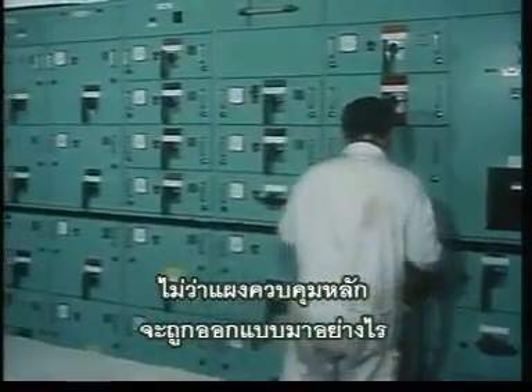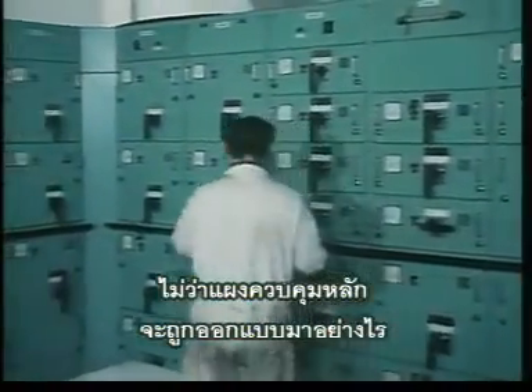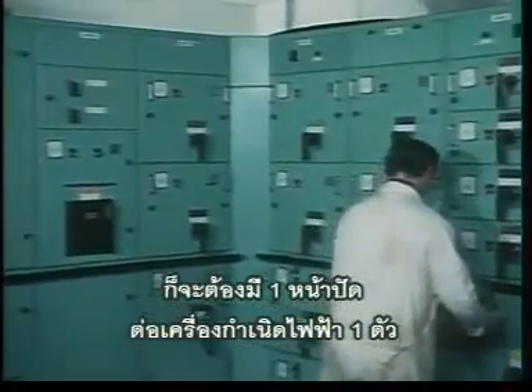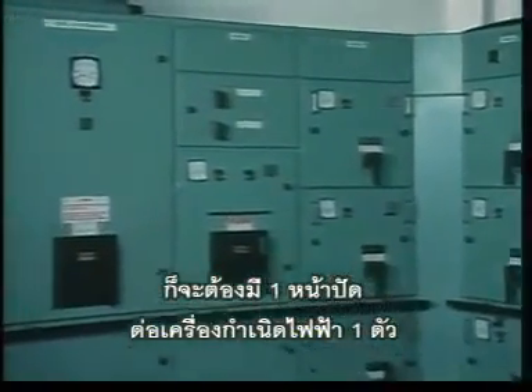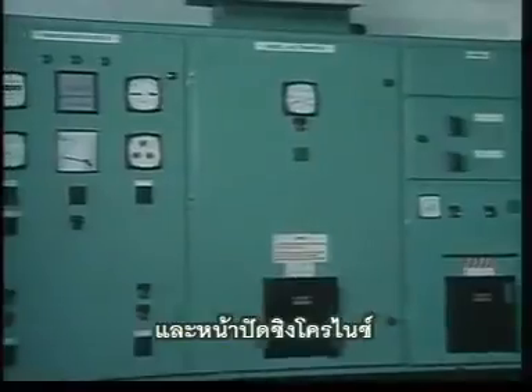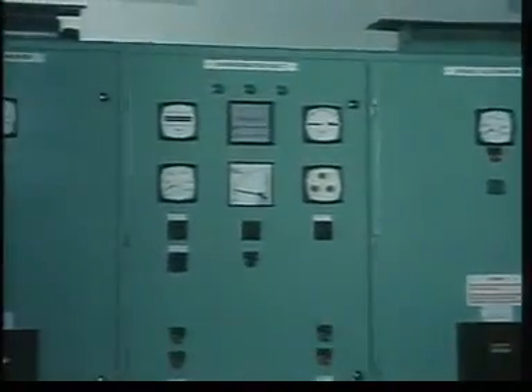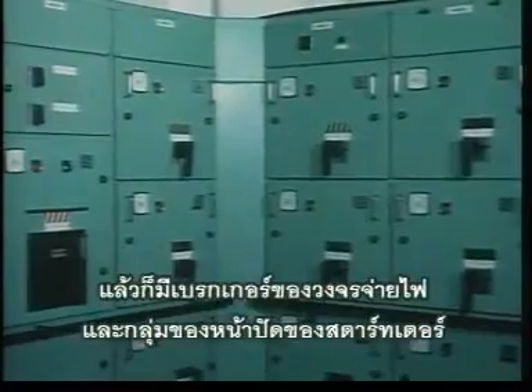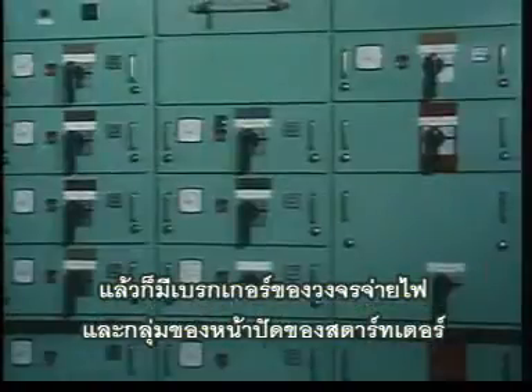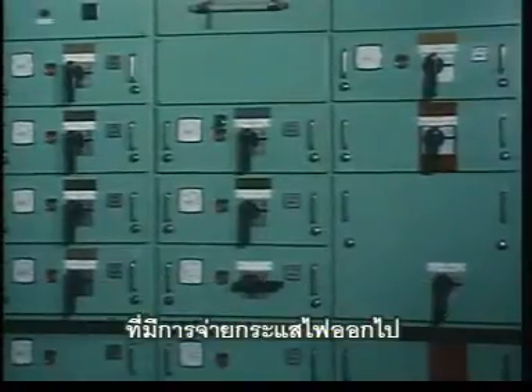Whatever the design layout of your main switchboard may be, you'll have one panel for each alternator feeding the board and a synchronizing panel. Then there are feeder circuit breakers and group starter panels through which the supply is distributed.